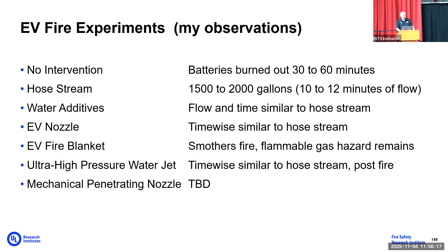EV fires are the same as internal combustion engine fires until the battery's involved. There's a good chance you won't know that until you try to suppress the cabin fire. You may be able to prevent the battery from thermal runaway if caught early enough. At worst, you cut the size of the fire in half. The pack often destroys all the cells anyway, flaming or not. When the battery is involved, the fires are not significantly faster, larger, or longer burning than an internal combustion engine vehicle. Wear your PPE, use exposure controls, and maintain existing guidance for decontamination. Nothing to the contrary was seen here. Be aware of stranded energy and do not attempt to disassemble, remove, or pierce a battery, and make sure to coordinate with the second responders and educate them.